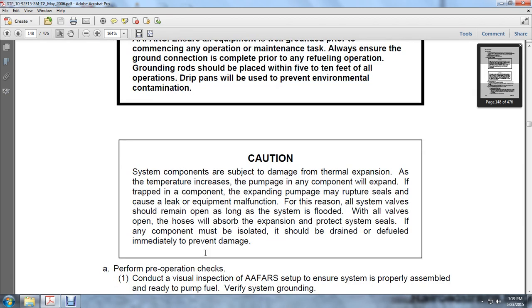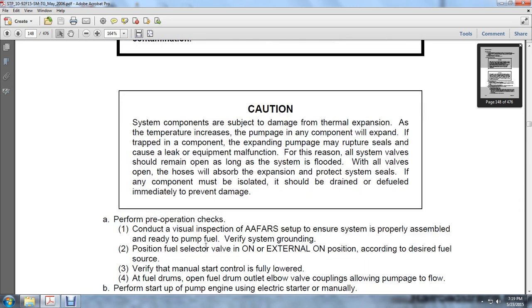System components caution. System components are subject to damage from thermal expansion. As the temperature increases, the pumpage in any of the components will expand. If it is trapped in a component, the expanding pumpage may rupture the seal and cause a leak, or the equipment may malfunction. For this reason, all system valves should remain open as long as the system is flooded. With all the valves open, the hoses will absorb the expansion and protect the system seals. If any of the components must be isolated, it should be drained and defueled immediately to prevent damage.